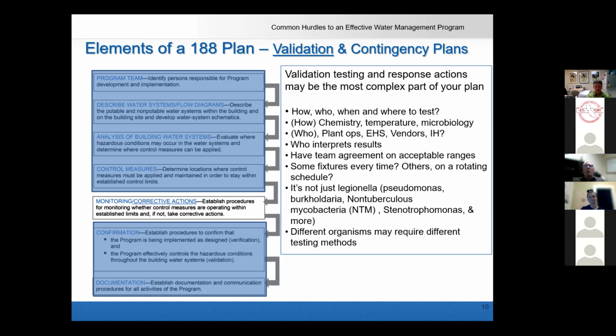So, and how are we going to do it? Are we going to test chemistry, temperature? Those are listed in the environment of care standard. So you probably need to do that. But even that, where are you going to test temperature? Are you going to test it down in the basement at the boiler? Or are you going to test it at the distal fixtures? If so, what's your thermographic method? Are you using a NIST traceable thermometer? Are you looking at how hot it gets and how long it takes to get that hot?